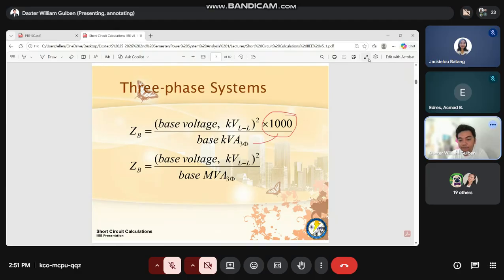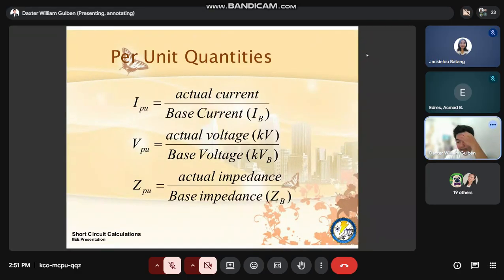Tapos yung per unit values nimo, per unit values is just a ratio of your actual value versus the base value. In this case, for current, the actual current over the base current. So in most cases, ato ang short circuit analysis, gagamit gid tawag per unit. Again, the reason why we're dealing with mega volt-amperes, kilovolts. So dagko kayo siya nga values. Kung ato na siyang gamiton, usually i-round off na to, mag-amplify ang ato ang error. So to avoid errors ato ang computations, we have to use the per unit values or basically the normalized values, no? So man ang concept gyud sa ato ang per unit quantities.